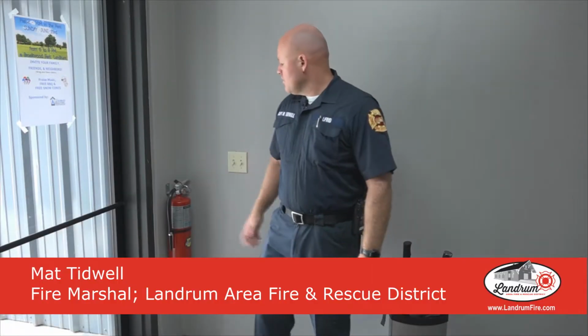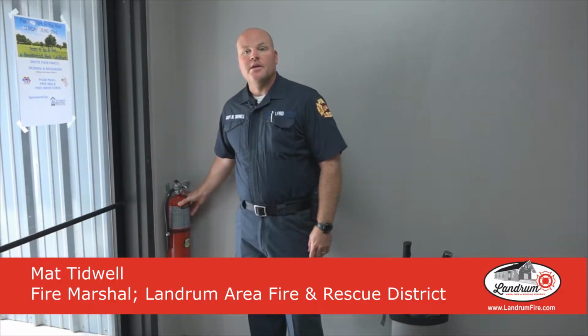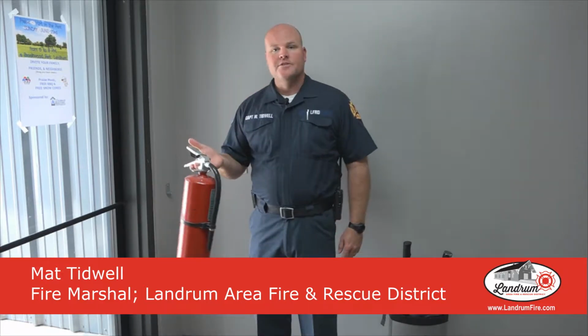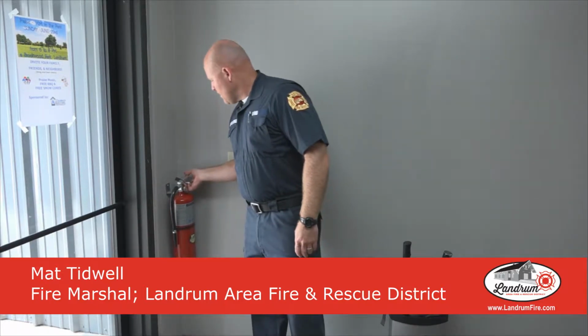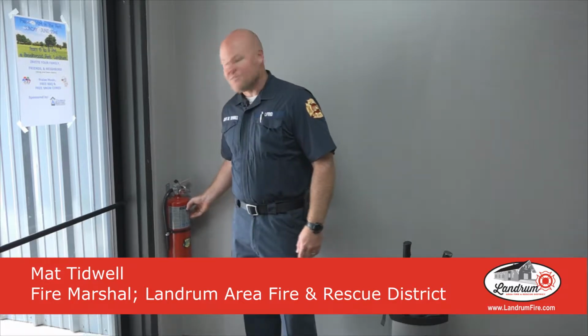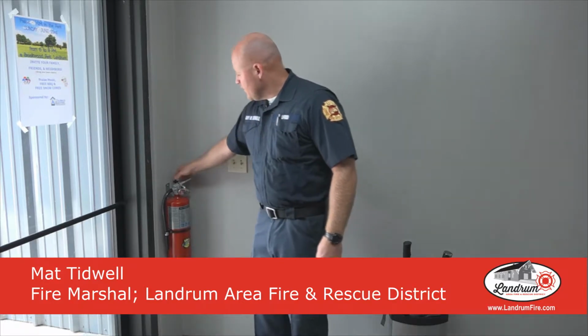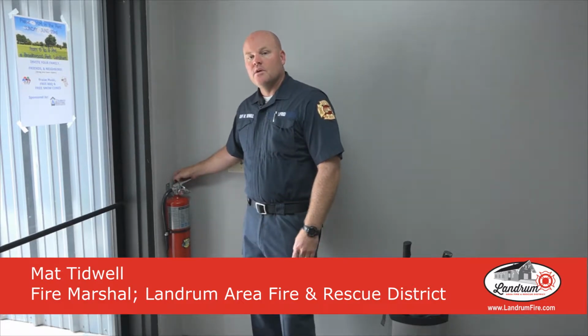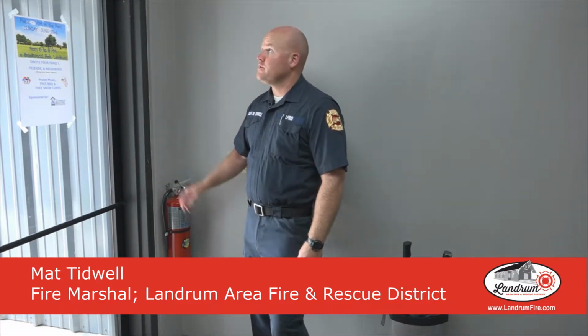Okay, moving right along. We're looking at a fire extinguisher. It is properly mounted. It is secure. It's easily accessible. So they get a check mark on the positive side on that one, and it is in the green, and they just had this tested. They actually have until October of 2019 to get that retested, so it's looking good.